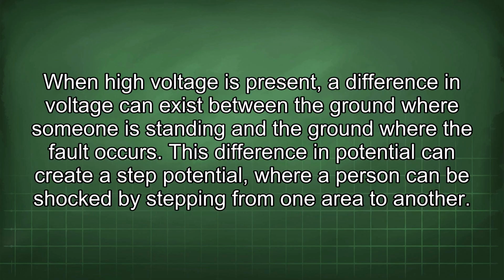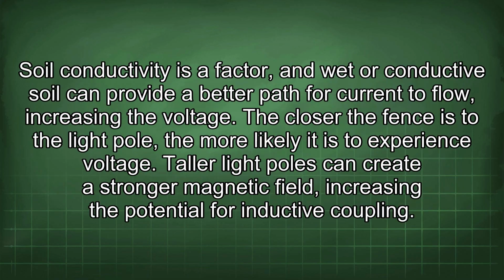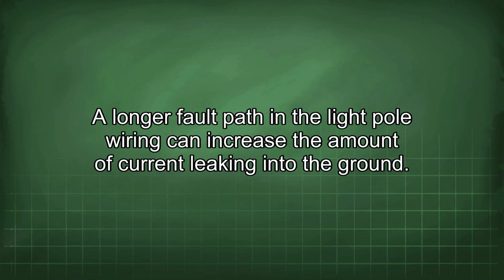When high voltage is present, a difference in voltage can exist between the ground where someone is standing and the ground where the fault occurs. This difference in potential can create a step potential, where a person can be shocked by stepping from one area to another. Soil conductivity is a factor, and wet or conductive soil can provide a better path for current to flow, increasing the voltage. The closer the fence is to the light pole, the more likely it is to experience voltage. Taller light poles can create a stronger magnetic field, increasing the potential for inductive coupling. A longer fault path in the light pole wiring can increase the amount of current leaking into the ground.